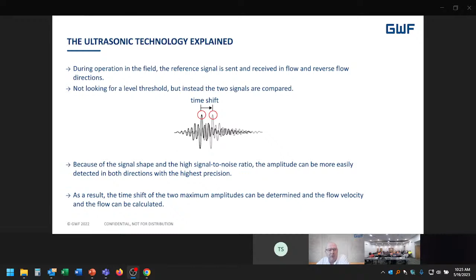We're seeing more paths being used in mag flow meters, and we're also seeing that more and more in ultrasonic measurement. With time reverse acoustics, we're able to give far better range. So we can start looking at leakage or otherwise, and understand what's going on. Obviously, with these things, we're looking more at powered devices. This isn't battery powered, this isn't a billing meter, this is a water management tool.